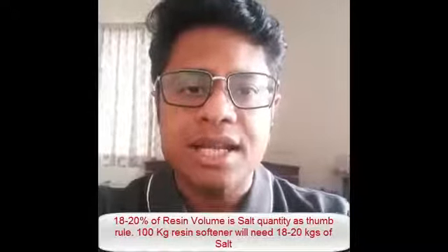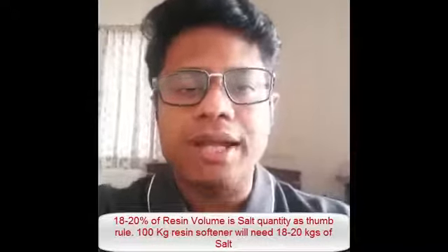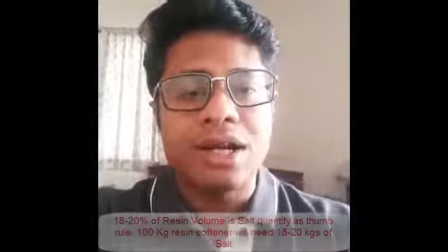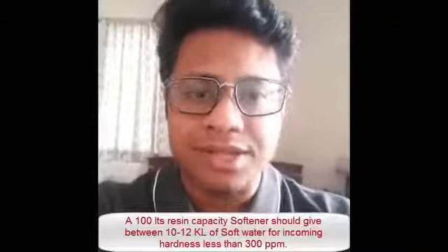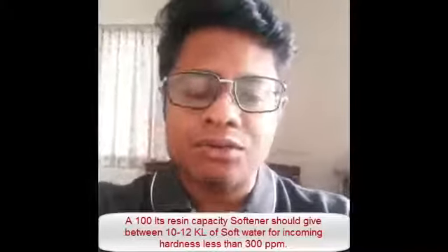A few people ask what quantity of salt they should put. The thumb rule is, for 100 liters of resin, you have to put 18 to 20 kgs of salt, dissolved to a concentration of 18 to 20%. If you put less salt, your softener regeneration will not happen efficiently. How much volume will a softener give? For 100 liters of resin, if your incoming hardness is say 300, it should give 8 to 10,000 liters of soft water. It can be extended to 14,000 liters if you don't want very soft water.